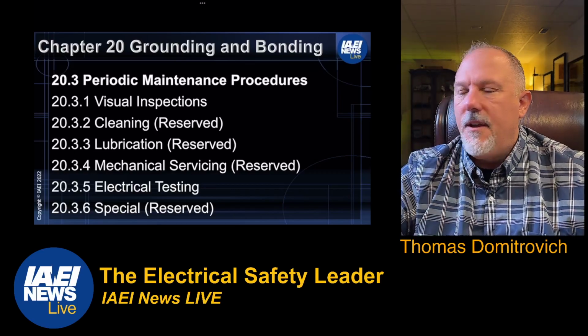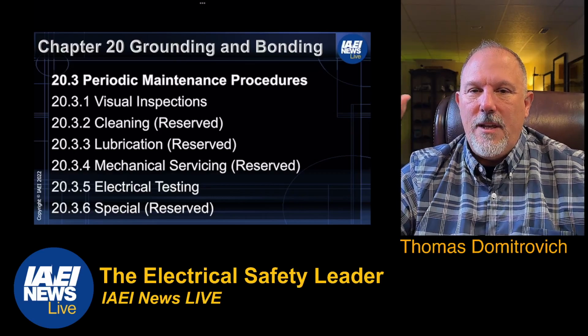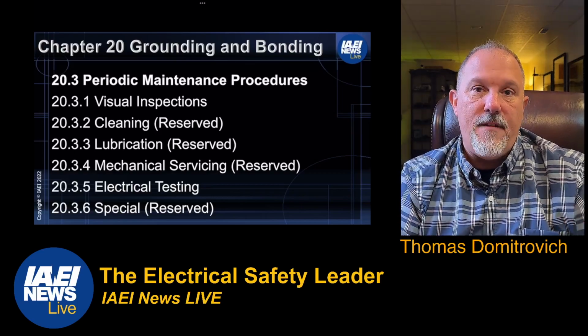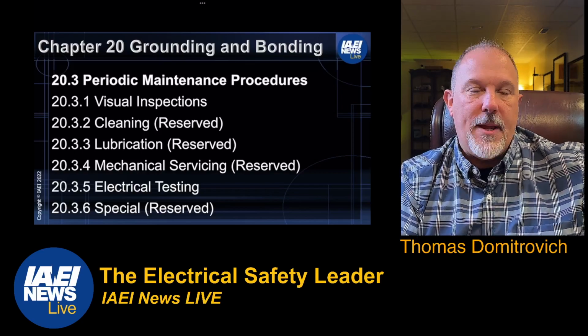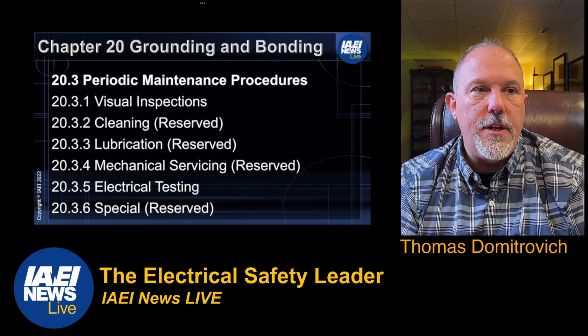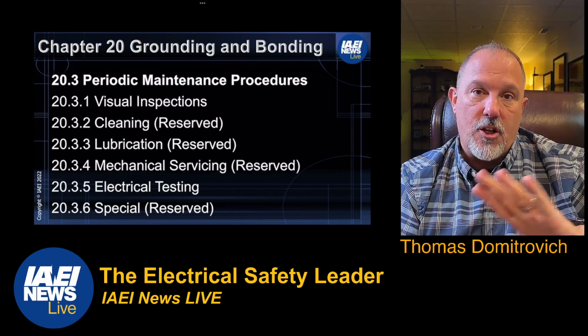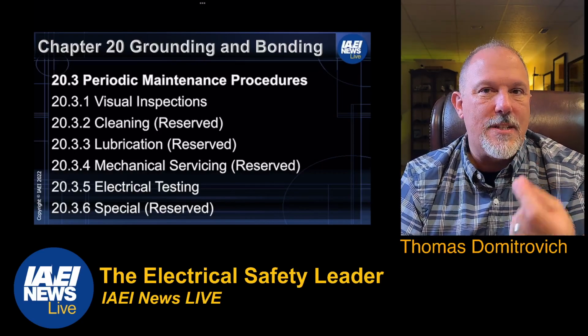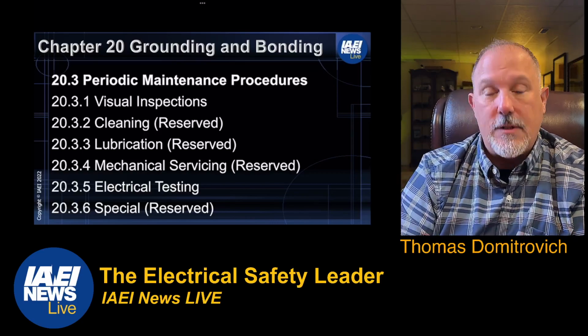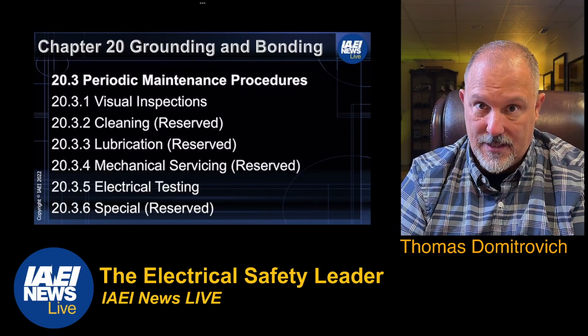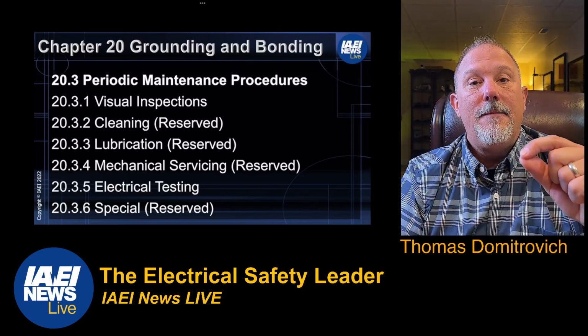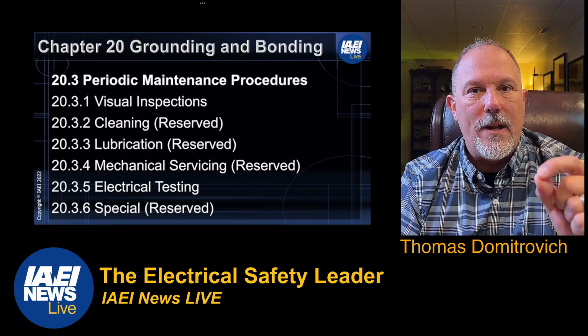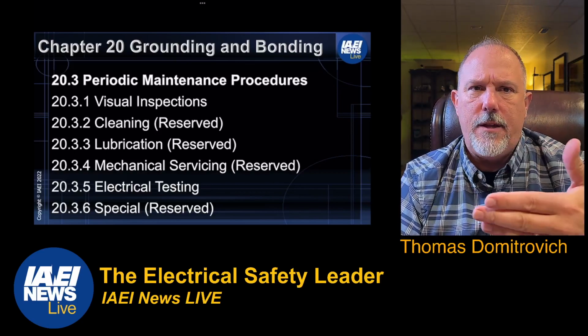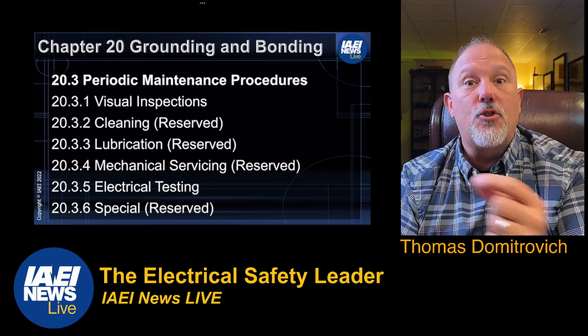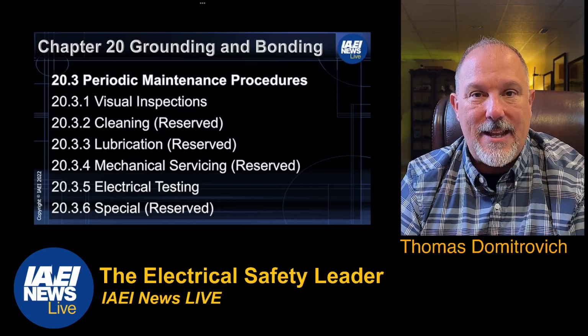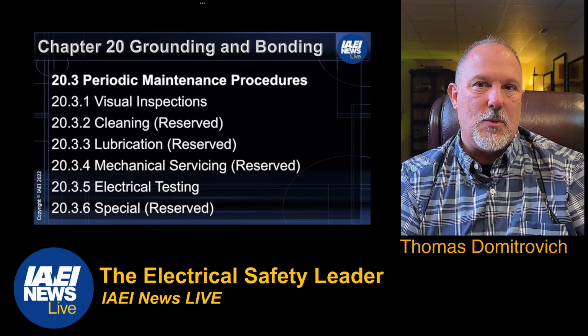That's the challenge with this topic. For example, one manufacturer may have a panel board that tells you you need to scrape paint off of the enclosure because maybe it was powder coated, in order to establish your ground. Your photovoltaic system grounding and bonding may have something similar. They may tell you exactly what equipment, bolts, screws, etc. can be or should be used to establish the bonding in that equipment and where the bonding has to occur.